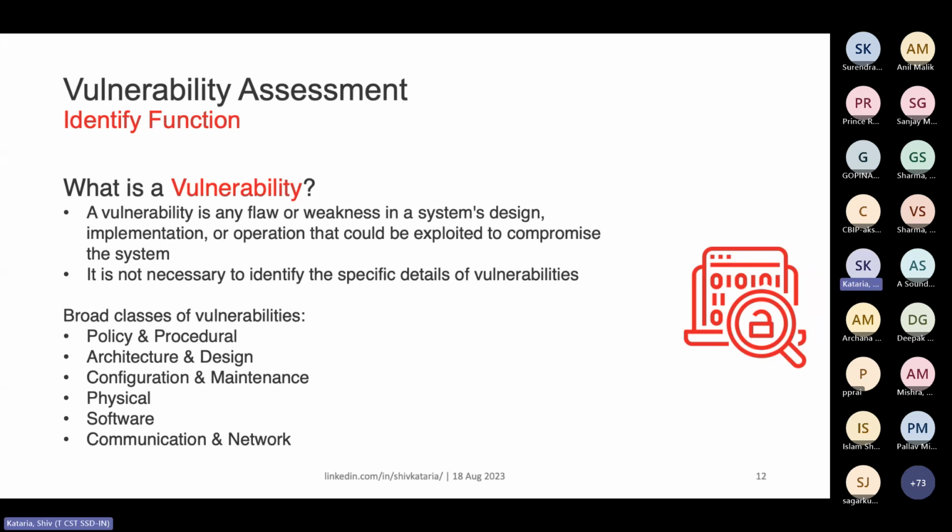Typically in the power sector, when I go and see, specifically in substations, what I have found is the username and passwords are generally written either on the screen of the computer, sometimes in the register which is there. And in the worst case, I have seen that there is a whiteboard and they have written the username and password on the board. These are again examples of policies and procedural vulnerabilities which are there.